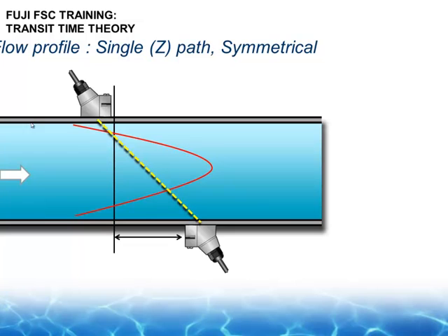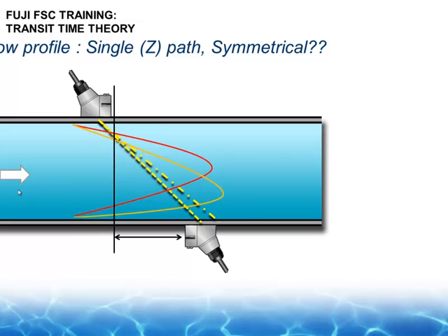But what if I had a short run of installation? Say I had an elbow over here. If I had an elbow over here, then my flow profile may actually be distorted. And it will also distort my signal. So the signal will actually be carried upstream or downstream depending on the application. And the only way I'll be able to see it is to move my transducer away from the calculated position. If I move it away from the calculated position, this is called prospecting. The only time you do this is when you can't get a reading at all.